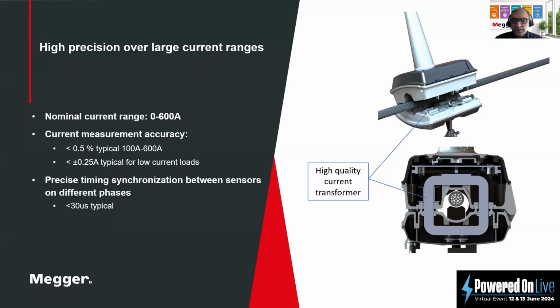The sensor is designed with two high quality CTs. One is for measurement of the current from the network, up to 600 amps with an accuracy of 0.5%, and synchronization between the sensors of typically 30 microseconds, which enables the sensor to find zero sequence. The other is for highly efficient power harvesting from the line, down to 1.5 amps.